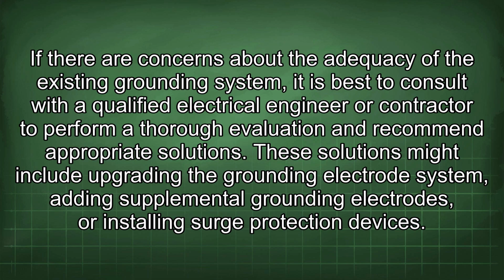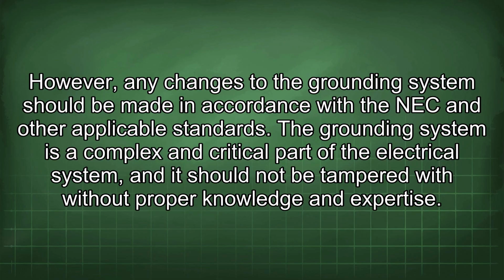If there are concerns about the adequacy of the existing grounding system, it is best to consult with a qualified electrical engineer or contractor to perform a thorough evaluation and recommend appropriate solutions. These solutions might include upgrading the grounding electrode system, adding supplemental grounding electrodes, or installing surge protection devices. However, any changes to the grounding system should be made in accordance with the NEC and other applicable standards. The grounding system is a complex and critical part of the electrical system, and it should not be tampered with without proper knowledge and expertise.